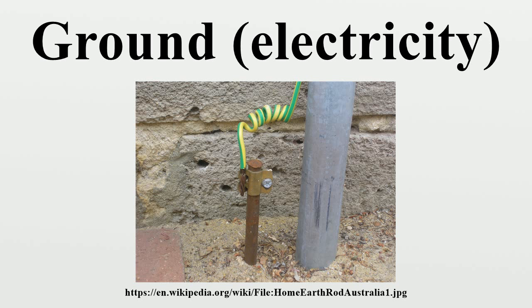Lightning protection systems are designed to mitigate the effects of lightning through connection to extensive grounding systems that provide a large surface area connection to Earth. The large area is required to dissipate the high current of a lightning strike without damaging the system conductors by excess heat. Since lightning strikes are pulses of energy with very high frequency components, grounding systems for lightning protection tend to use short straight runs of conductors to reduce the self-inductance and skin effect.